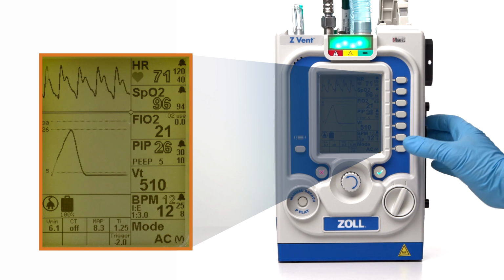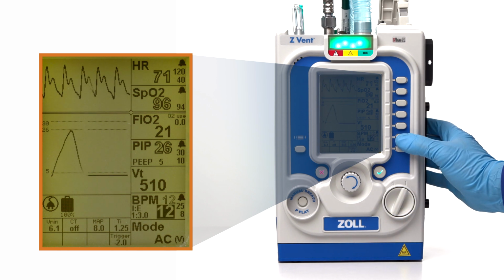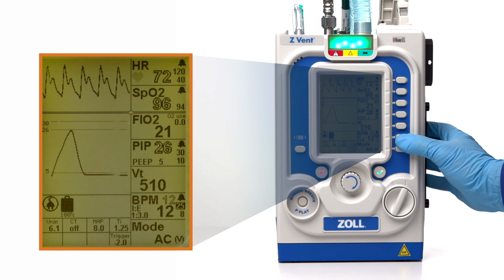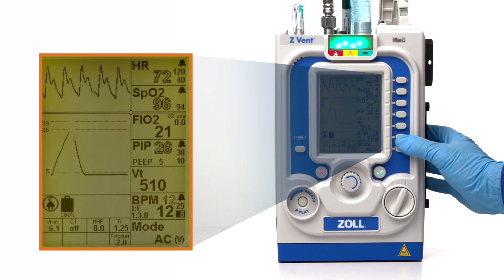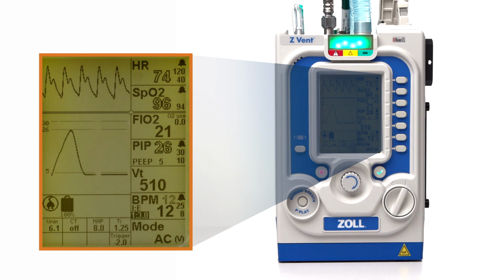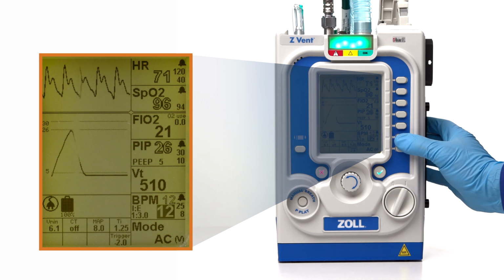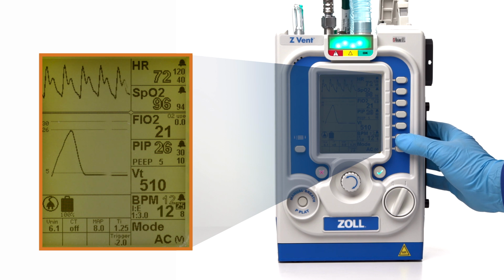Press the parameter button once to change the desired BPM, twice to change the high breath rate alarm, three times to change the low breath rate alarm, and four times to change the I to E ratio. If desired, the user may inverse the I to E ratio. To do so, press the parameter button four times to cycle to the I to E ratio value.